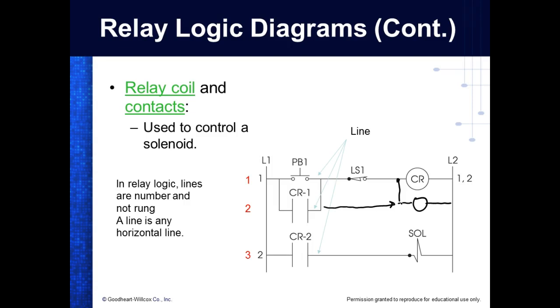So now I can reference things. I can say go to line number 200 - not rung number 200, line number 200. We get on the left side, fall down and find the line number, then come over and see a relay, say 2, 5, 20, 50 on the right side. Then I know where the contact's controlled by that relay - I know the line number, not the rung number, because a rung might be this long, since we could have 15 parallel contacts or all kinds of stuff.